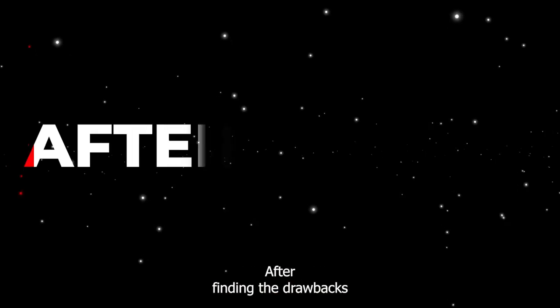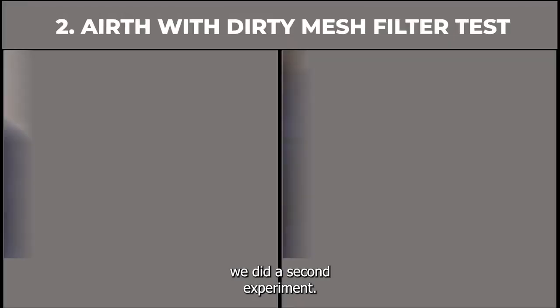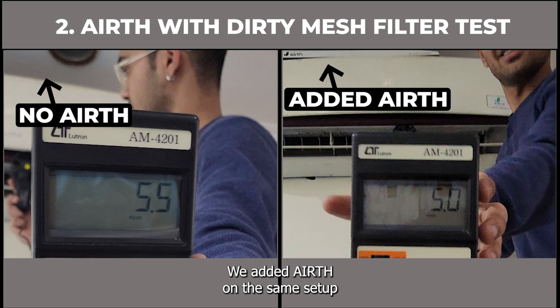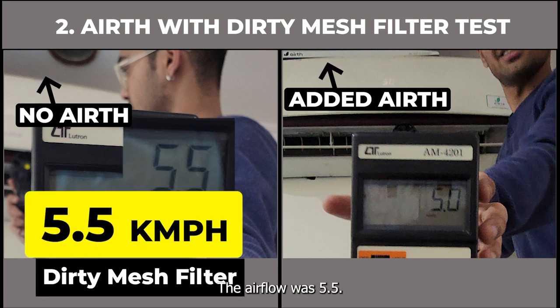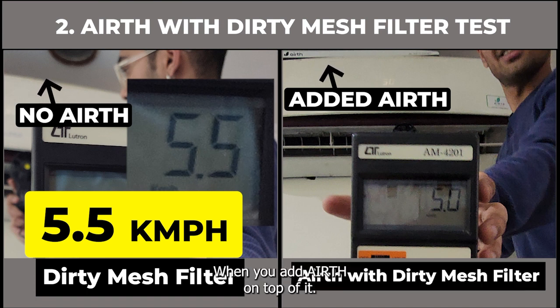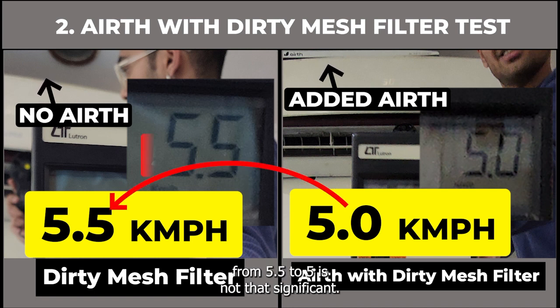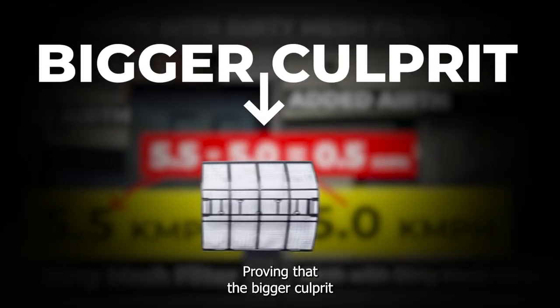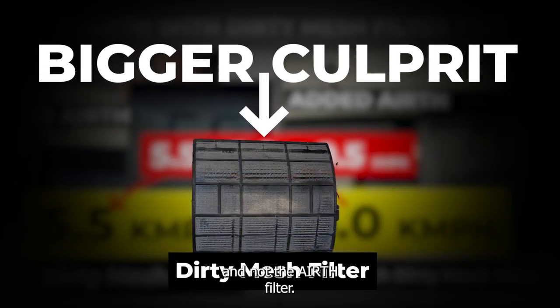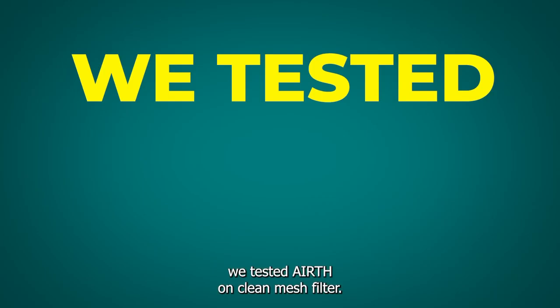After finding the drawbacks of dirty mesh filters, we did a second experiment. We added AIRTH on the same setup. As we know, with dirty mesh filters the airflow was 5.5. When you add AIRTH on top of it, the airflow reduces to 5. If you notice, this drop from 5.5 to 5 is not that significant, proving that the bigger culprit was your dirty mesh filter and not the AIRTH filter.